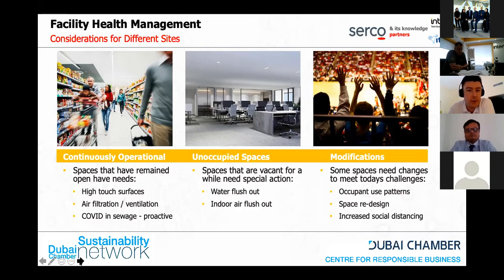Unoccupied spaces, so those that have perhaps been shut down during the pandemic - I'm sure several hotels and hospitality venues which have been completely out of use for months, if not over a year now, are going to have particularly special needs, things like potable water. In buildings where occupancy has been down 5-10% of normal, water tank storage on site will still have been 100%, so turnover and consumption may be several weeks instead of days. That can present problems with Legionella and water quality inside the building.